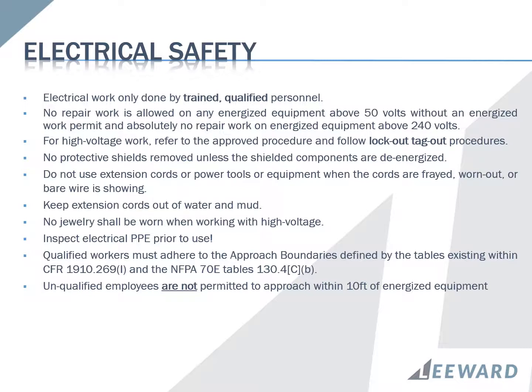Keep extension cords out of water and mud. No jewelry shall be worn when working with high voltage. Inspect electrical PPE prior to use. Qualified workers must adhere to the approach boundaries defined by the tables existing within the CFR 1910.269(I) and the NFPA 70E tables 130.4. Unqualified employees are not permitted to approach within 10 feet of energized equipment. This is to be measured in relation to a 10-foot measurement extending from personnel in any given direction to any conductive objects.